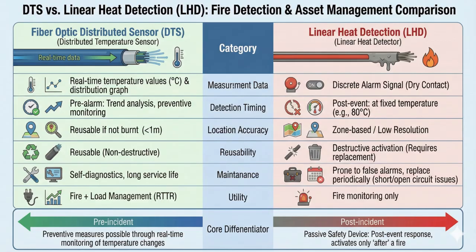When comparing DTS with linear heat detection (LHD), the direction is fundamentally different. LHD is mainly for fire detection and triggers only when a set temperature is reached, so the data is limited. DTS provides real-time temperature distribution and trend analysis, enabling early anomaly detection and higher location accuracy. It also offers advantages in maintainability and reusability, and its use extends beyond fire detection to RTTR and asset management. In short, DTS is not a passive safety device. It is an active asset management tool.